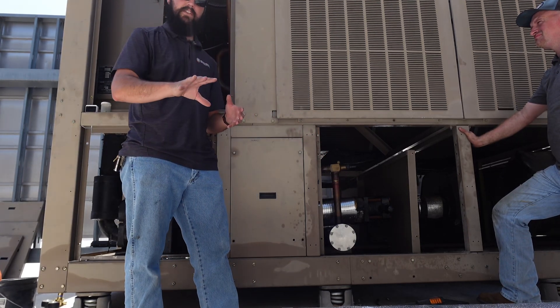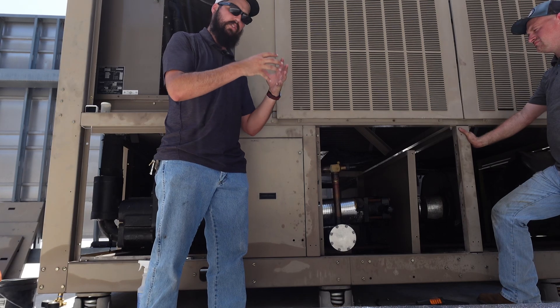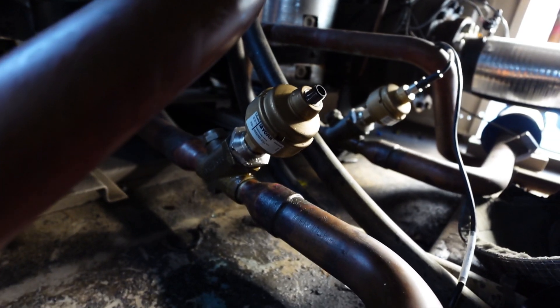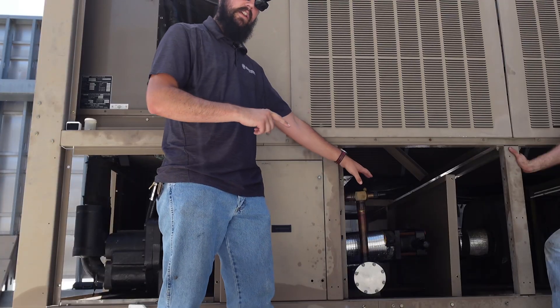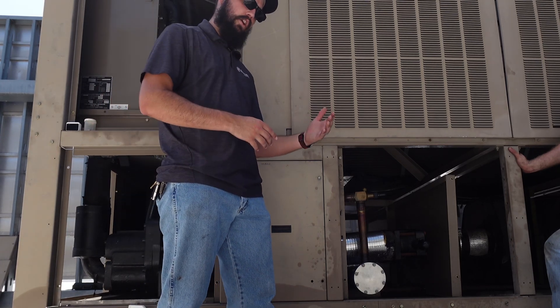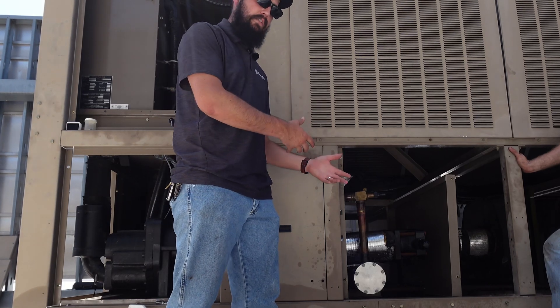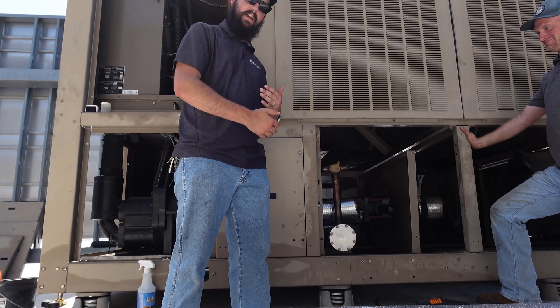He came over and looked down inside and saw the feed valve spewing out pretty dramatically. This was three hours in — it took three hours for just the right conditions to form. We had a severe leak on the discharge, which we didn't cause, but we also had a leak open up at the threads where the head and valve body meet on the feed valve itself. We did just replace that valve about a month ago, so we have to take responsibility on that. We offer a 90-day workmanship warranty — that valve or that seam failed within that 90-day period, so we hold some responsibility for this job's failure.